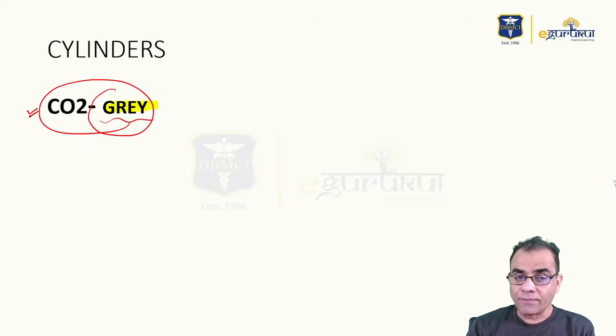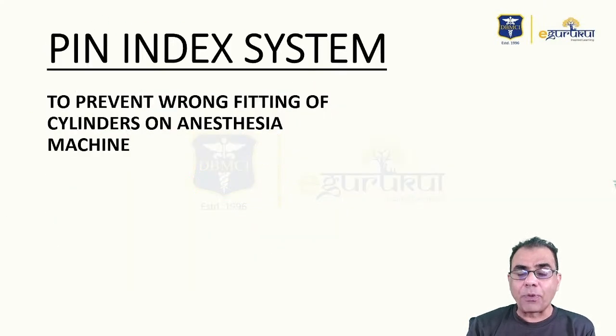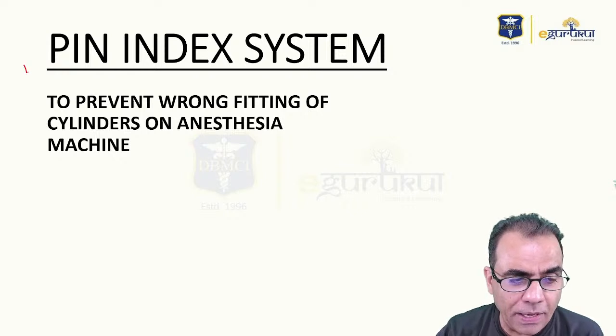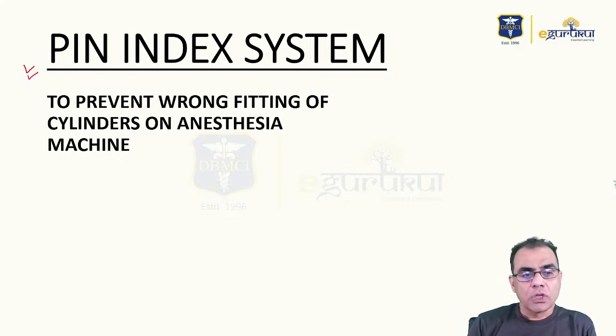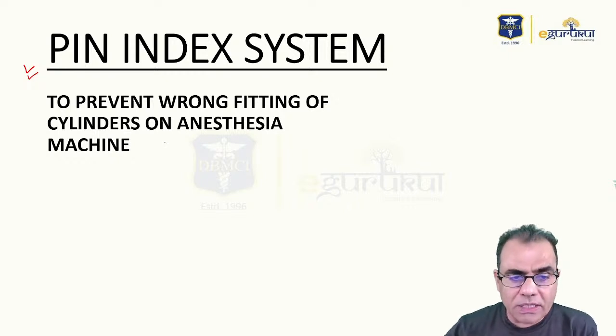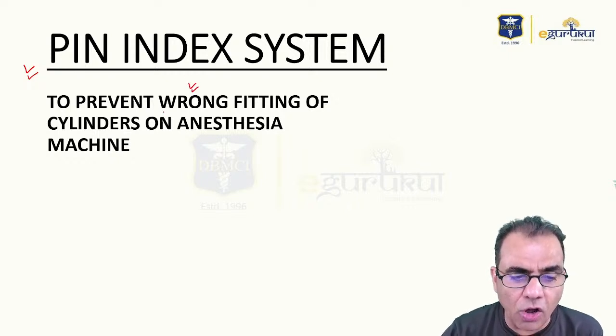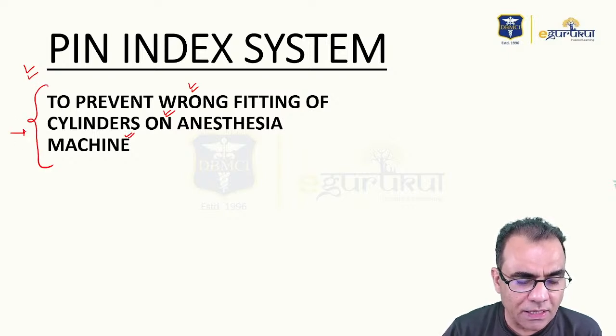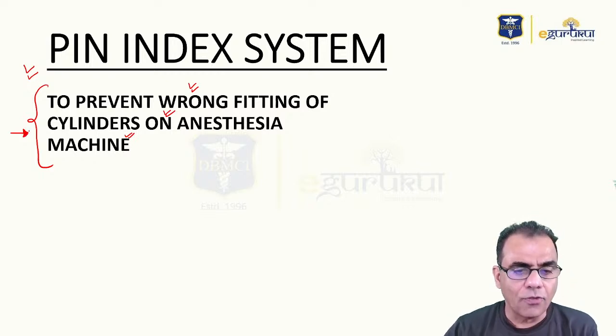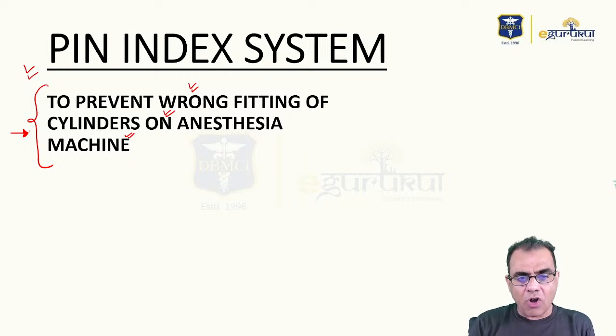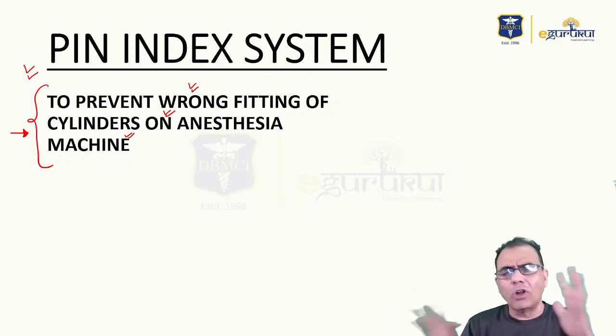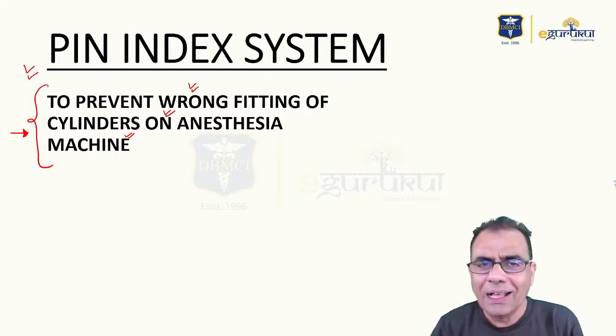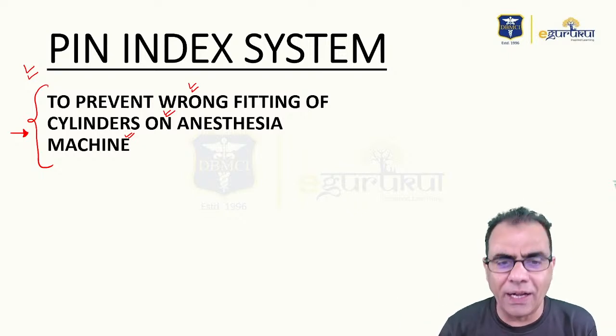And that portion, that interface which prevents wrong supply of cylinders to the anesthesia machine, is called the pin index system. So what is the pin index system? It is to prevent a wrong fitting of cylinders on the anesthesia machine. So the pin index system is the system used to prevent wrong fitting of cylinders on the anesthesia machine. There is no need to go into all those details, but just for your understanding, I'll make you understand what exactly this pin index system is.